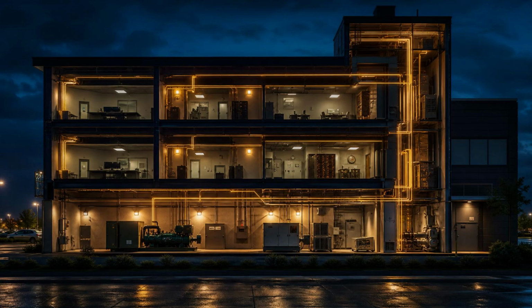Fuel delivery is the final piece of the fuel system picture, and it is worth acknowledging because it represents the point where the emergency power system's readiness extends beyond the building itself and into the relationship between the facility and the world outside it. A fuel tank, however large, holds a finite supply. For a short outage, a few hours, perhaps half a day, the on-site storage is typically more than sufficient. But for a long outage, the kind that follows a major storm or a widespread grid failure, or any event that disrupts the utility supply for days rather than hours, the fuel in the tank will eventually run low.